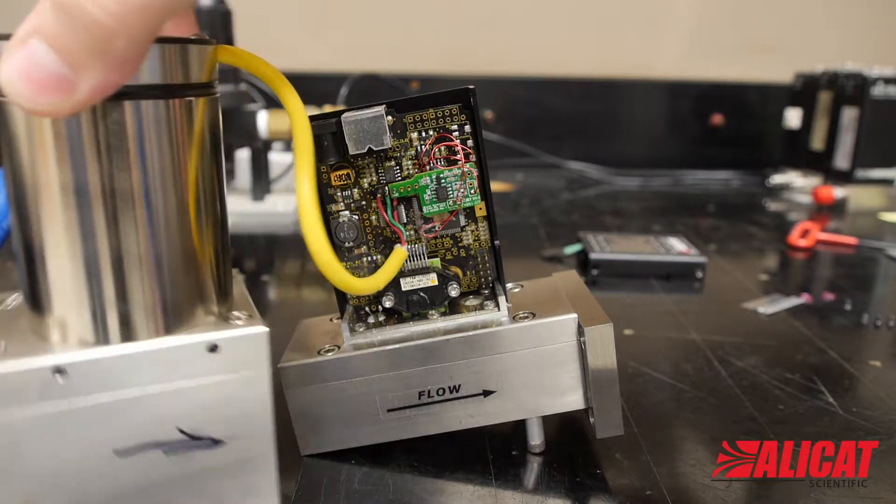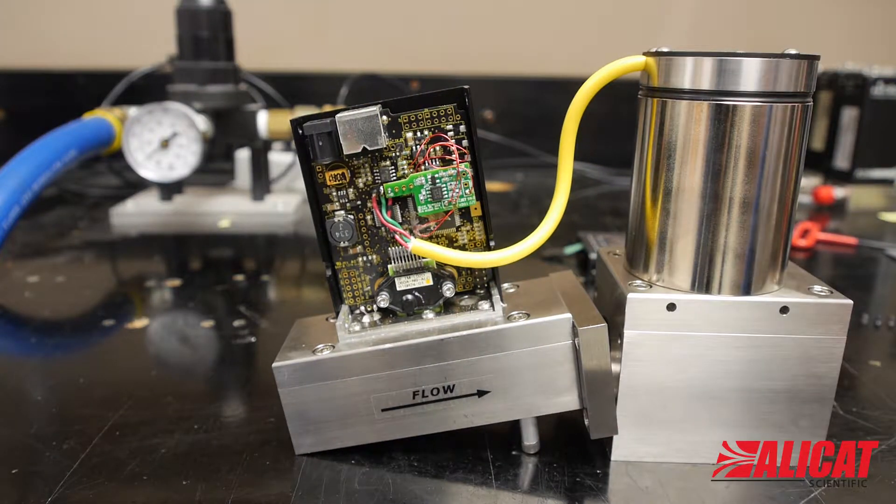With everything removed, move the Rolamite valve to the other side's case cutout. You will find at this point that the arrow is on the wrong side of the valve.